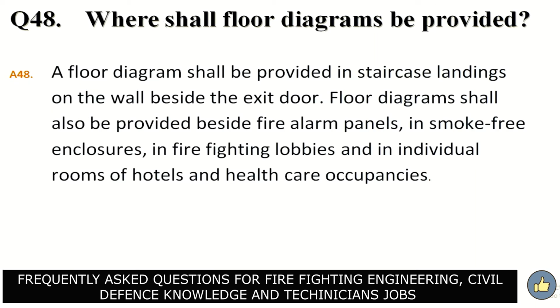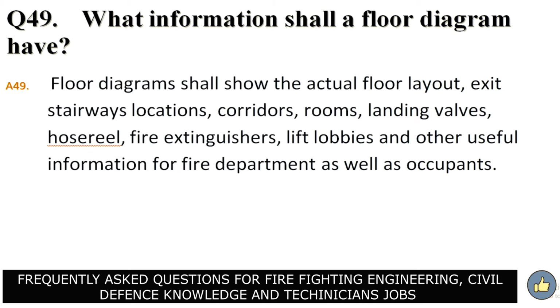Where shall floor diagrams be provided? A floor diagram should be provided in staircase landings on the wall beside the exit door. Floor diagrams shall also be provided beside fire alarm panels in smoke-free enclosures, in firefighting lobbies, and in individual rooms of hotels and healthcare occupancies. What information shall a floor diagram have? Answer. A floor diagram shall show the actual floor layout, exit stairways locations, corridors, rooms, landing valves, hosereel, fire extinguishers, lift lobbies, and other useful information for fire department as well as occupant.